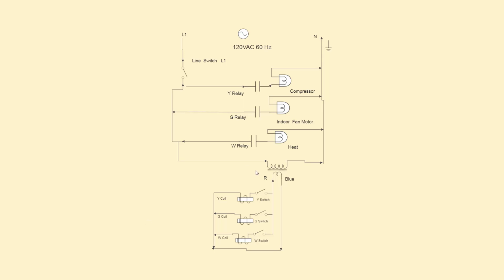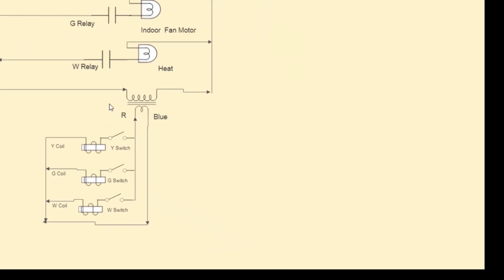Now, what's happening in the 24 volts? Remember, in HVAC, we use 24 volts AC to control high voltage. Usually it's 220 volts, in some cases 440 volts, but definitely 220 volts for residential work. These 24 volt wires are very small. They are thermostat wire. And instead of being 16 gauge AWG, they are 18 gauge AWG. And all the wires on your low voltage piece of your board should be this 18 gauge wire, and the Y wire should be yellow, and the G wire should be green, and the W wire should be white, just to keep track of everything.